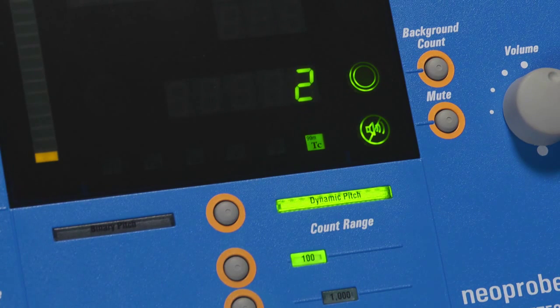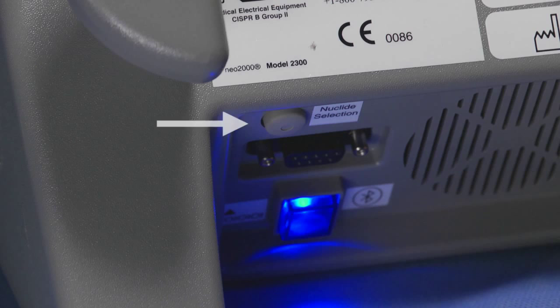The selected radionuclide is displayed on the console along the bottom of the screen. To change the radionuclide, push the nuclide selector button located at the rear of the unit. The system will cycle through the available radionuclides.